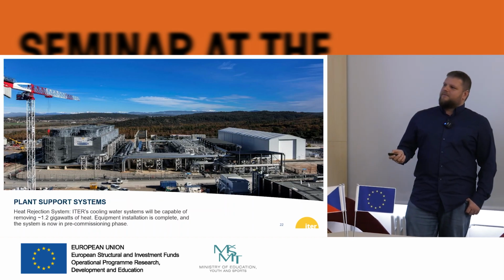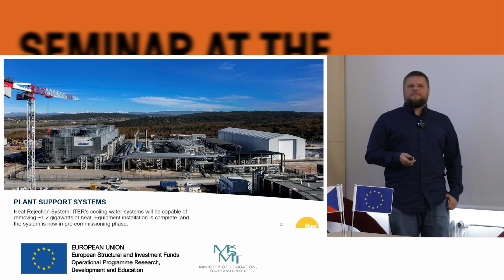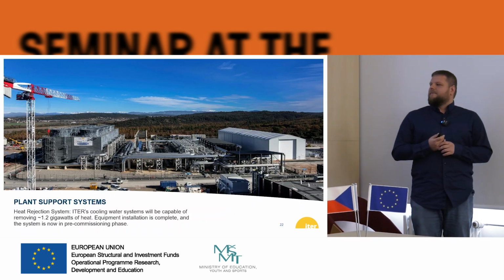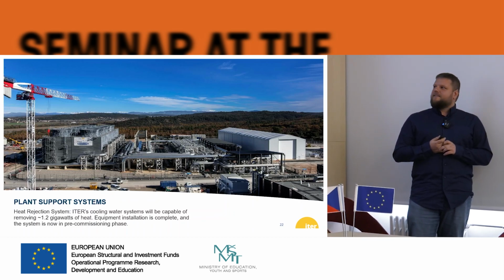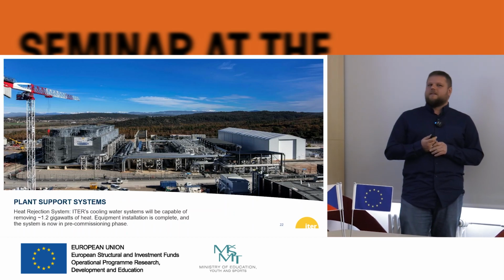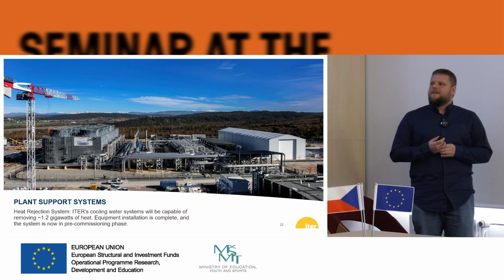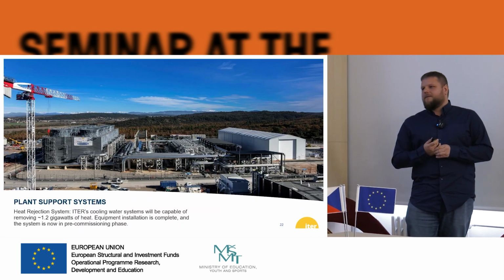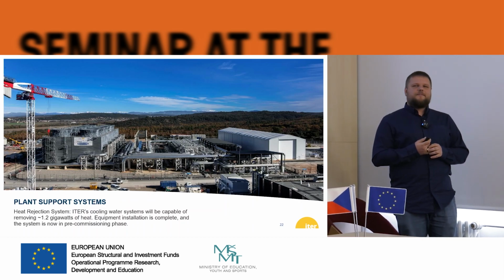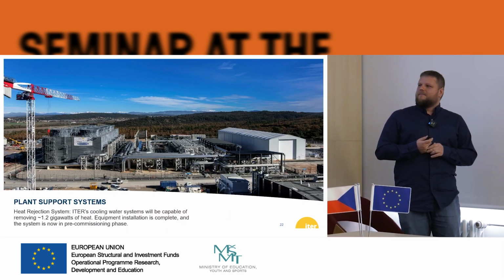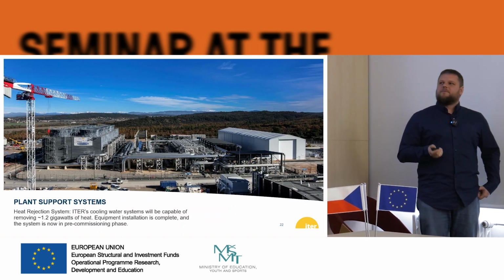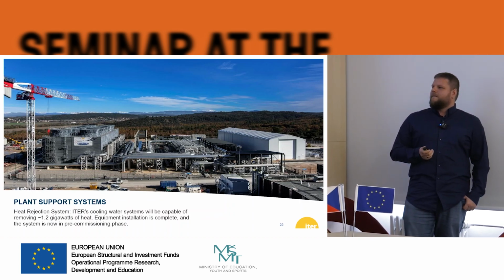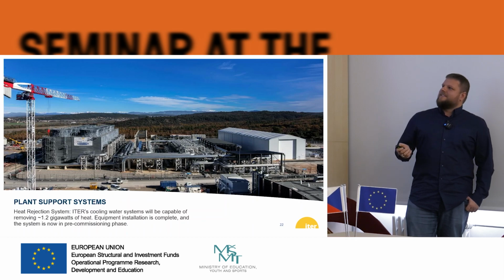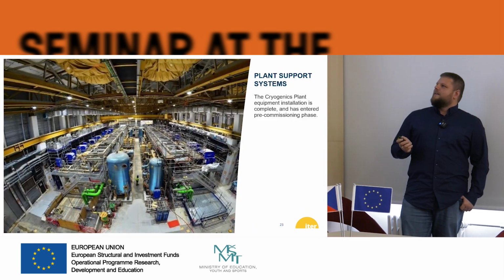That goes for any other heating or accompanying system, which is why we have 1.2 gigawatts of heat capacity to be removed. In reality it will probably be less, depending on how ITER performs, for example how high a power is achieved. Right now ITER is designed for 500 megawatts, but it's quite possible that at some point it will be refurbished to go even further, so the heat rejection system will be ready for that.